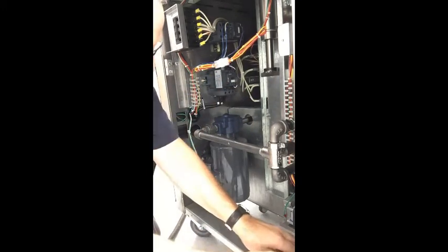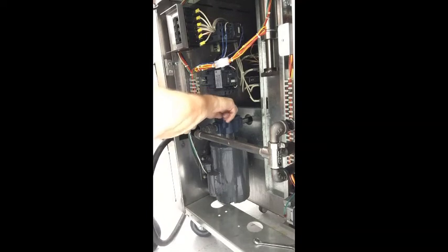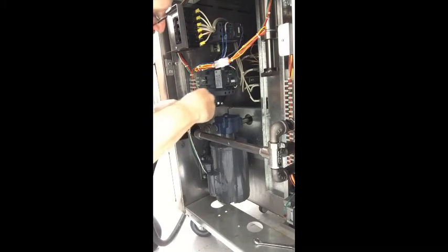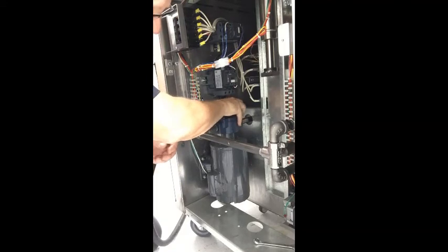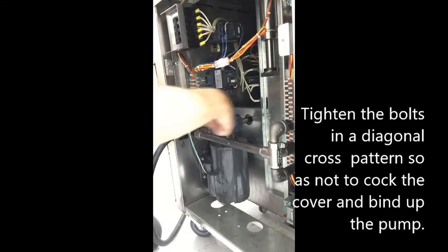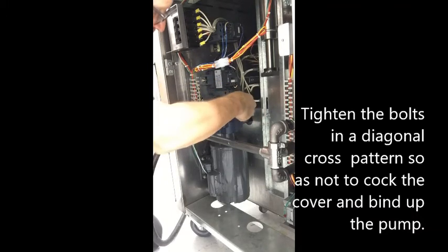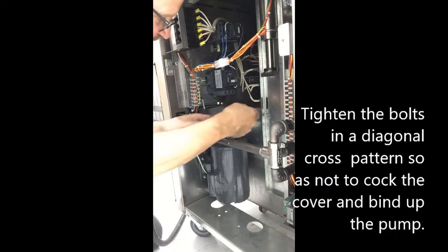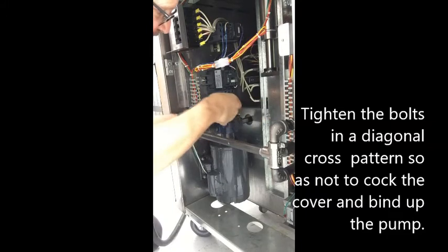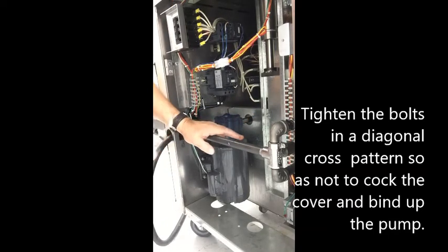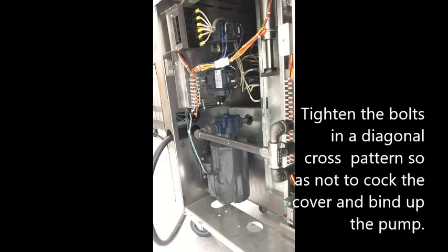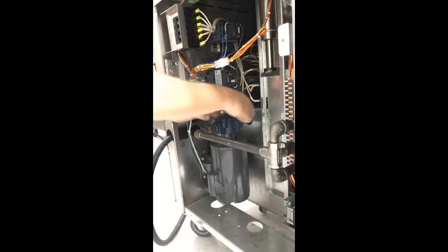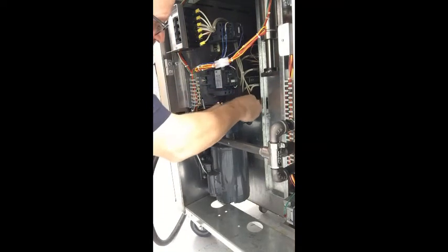Okay, push her down. We're going to put in the four bolts. You want to run them in finger tight. Once you get them in finger tight, then just a little snug. When you feel a little bit of pressure on there, then you want to stop. And make sure that you're going in a crosshatch motion. Do not just tighten up these two over here on one side. You'll cock that sideways and then it won't work for you. Now that I've got those just snugged up, I'm going to turn the pump on while I finish tightening those up. Okay, now that the pump is running, finish tightening these up.